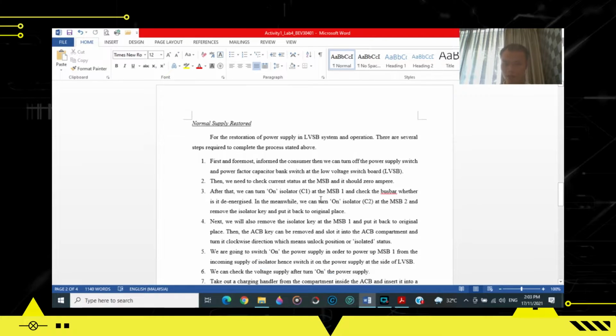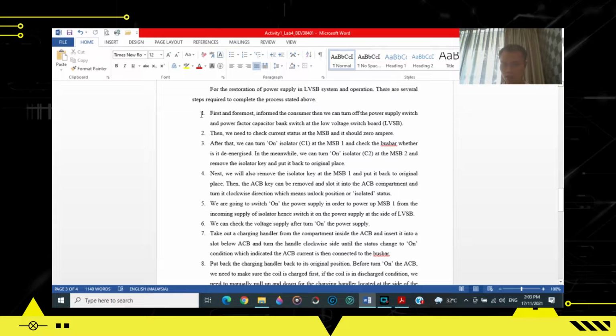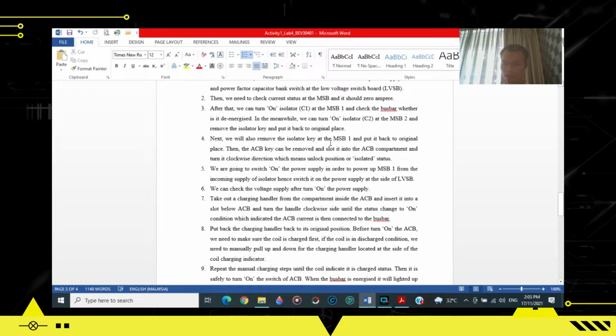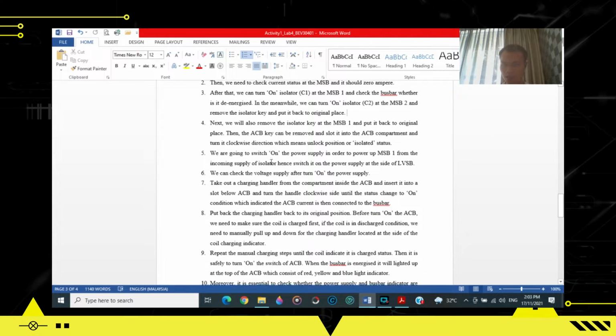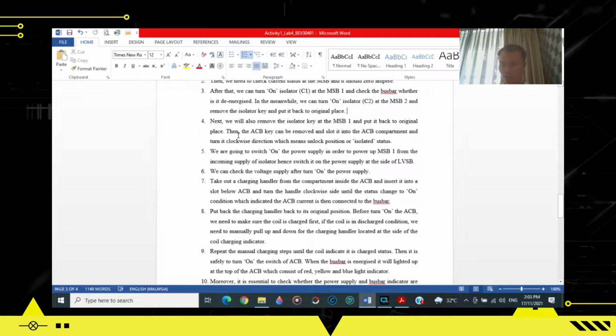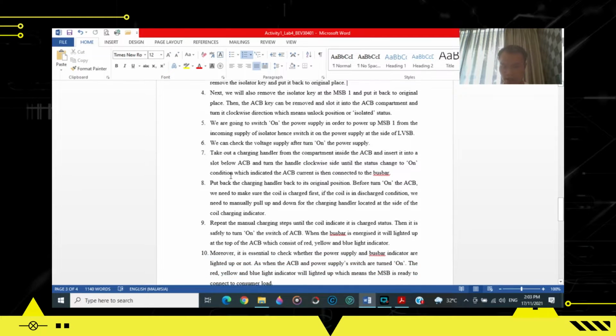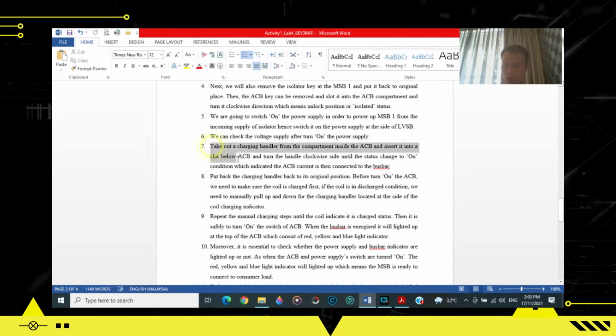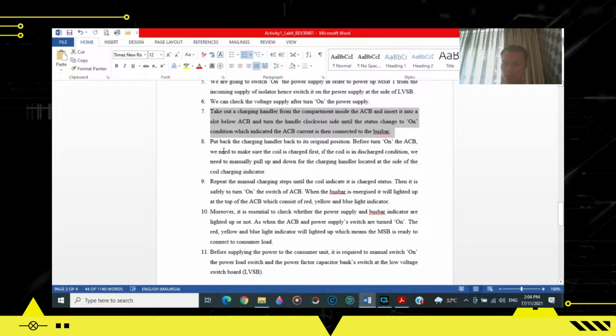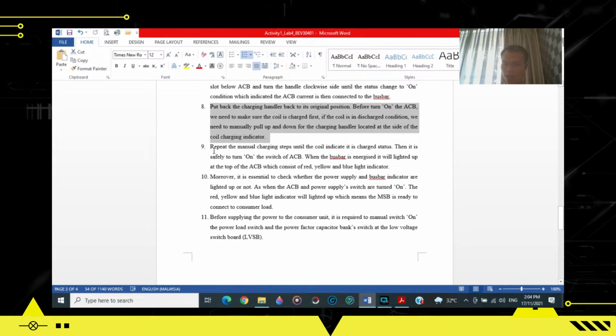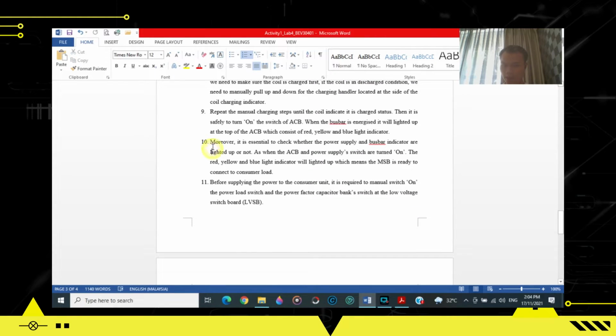Okay. So like I've said, we're going to turn off first in order to check all the equipment, and then we're going to turn on the isolator C1 and MSB1, check the bus bar, and all the keys need to be removed and placed back to the MSB1 and 2, the keys need to be placed back to the original place, and then we're going to remove the ACB key and slot it back to the ACB. And then we're going to use the charge handler to charge it back clockwise. We'll make sure that everything is flowing for the bus bar. The charging indicator will light up, and we're going to turn on the ACB.